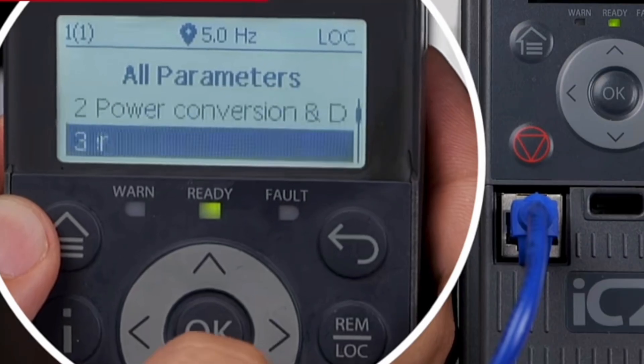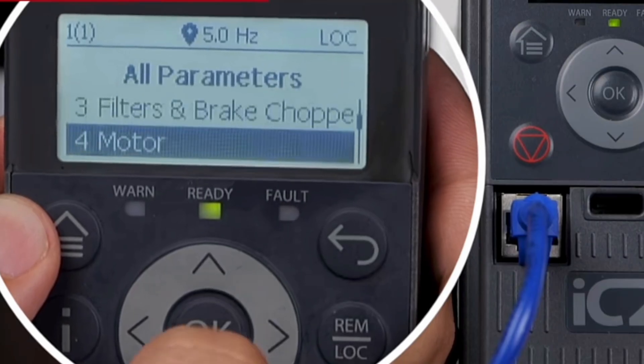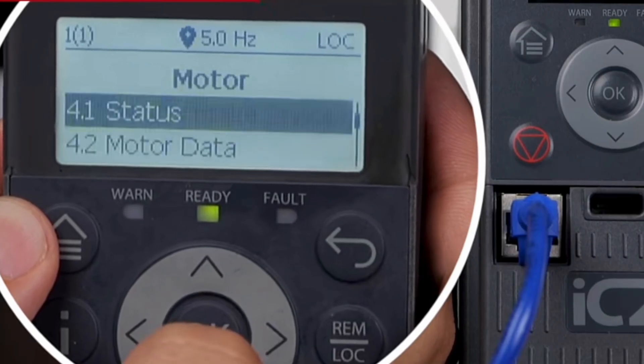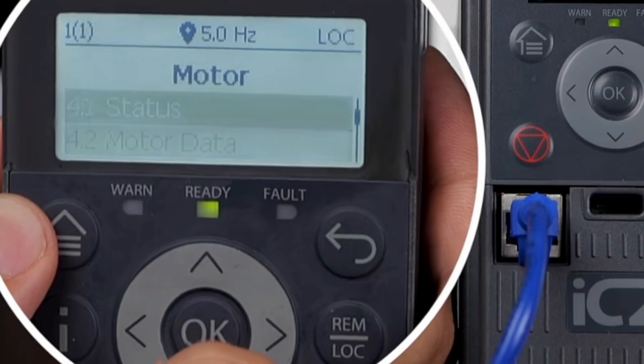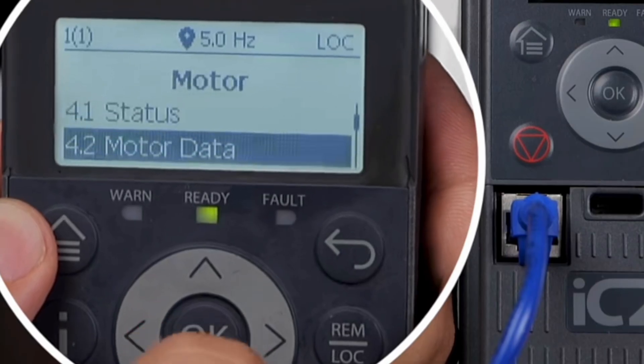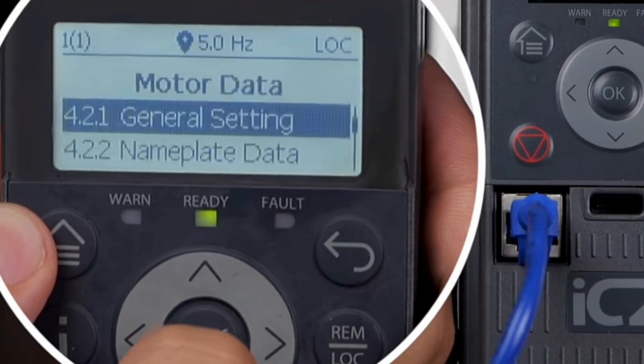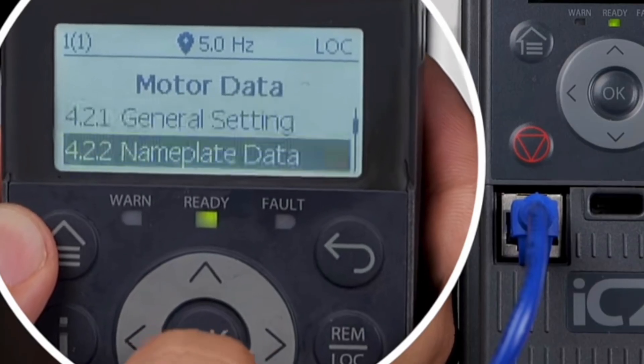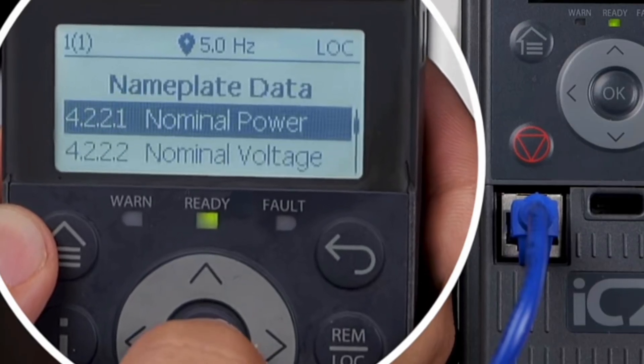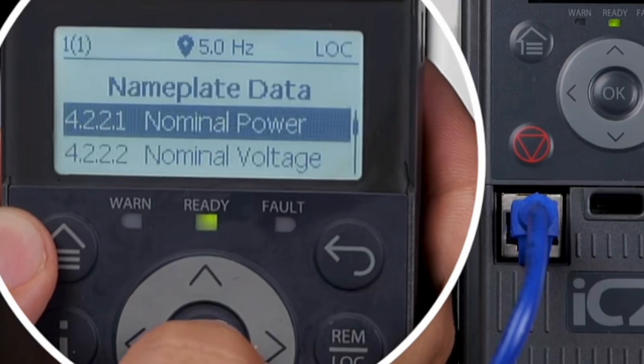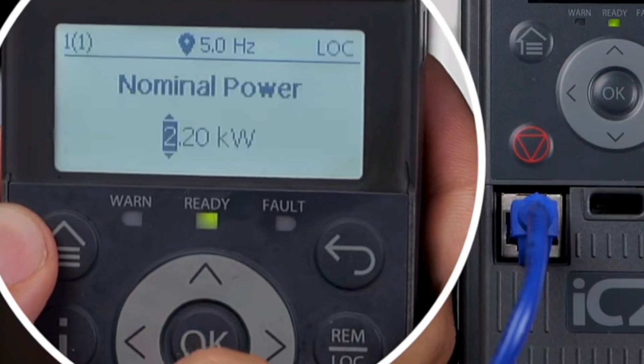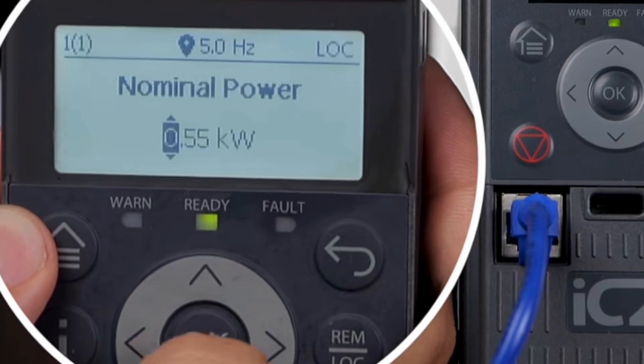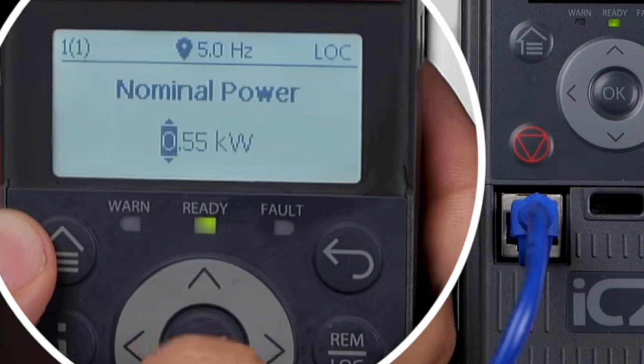Enter the parameters setting and find the fourth parameter group, and select parameter 4221. Set the nominal power of the motor to 0.55 kilowatts.